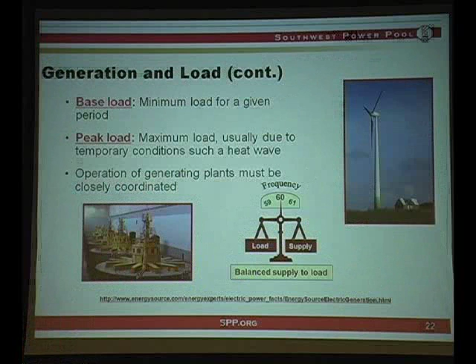Okay, transmission, which is what we're here to focus on. One of the neat things about electricity is we use AC, alternating current, which allows us to transfer or change voltage levels so smaller wires can carry a lot more power. For example, a 1-inch copper bar carrying 20 megawatts needs to be 1 inch thick at 18,000 volts. But if we change the voltage to a 500 kilovolt line, our amperage drops to 40 amps for the same 20 megawatts.